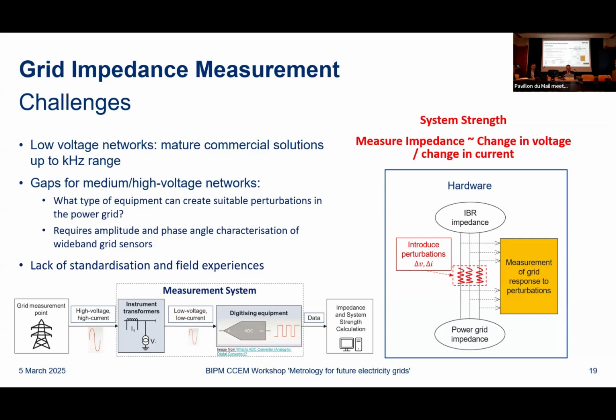But from the measurement point of view, you need your instrument transformers to be characterized. You need to know the amplitude error and the phase angle, and you need to know that across the frequency range. Because for the impedance we're talking about a difference measurement, it becomes even more important than for some other applications. Even a relatively small ratio error matters: if you're measuring a small difference in your voltage, let's say 5%, then a 1% amplitude error is already potentially a 20% error in your measurement, in simple terms. We're going to hear a bit more about characterization of the frequency response of instrument transformers from Mario. It's a highly important topic, and it also links into power quality phenomena.